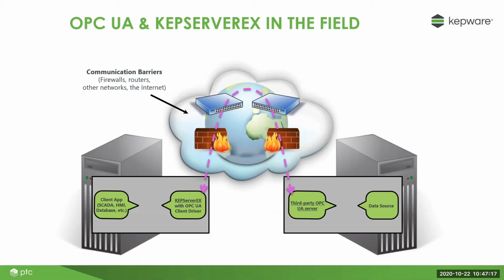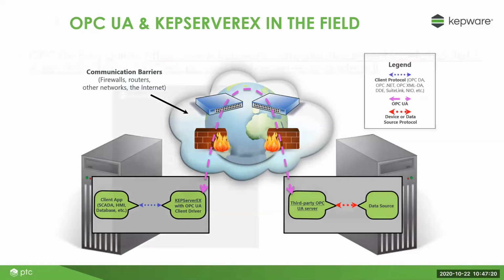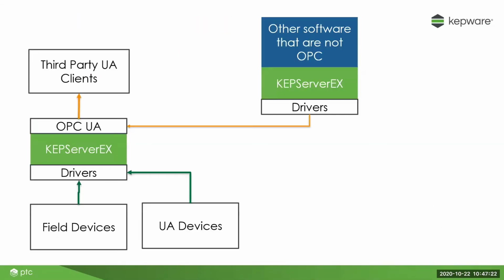What we are going to do in this demo is a UA client, a KEPWARE to KEPWARE connection. Why you'd want to do this could be a simple reason such as needing to aggregate various data into a standard SCADA software that doesn't support OPC or any of the protocols. As long as they don't support OPC UA, you're stuck. So you can use the UA client driver to pull data across various KEPWARE or other third-party UA servers.